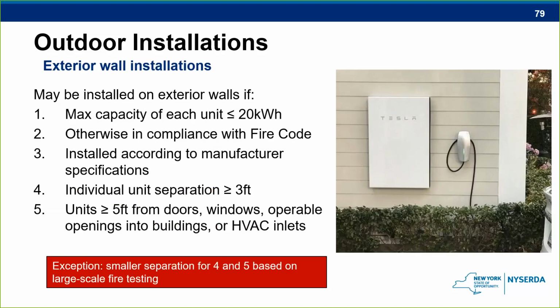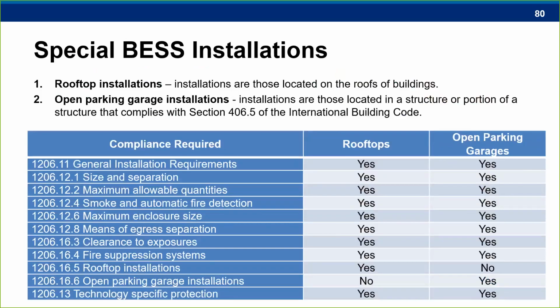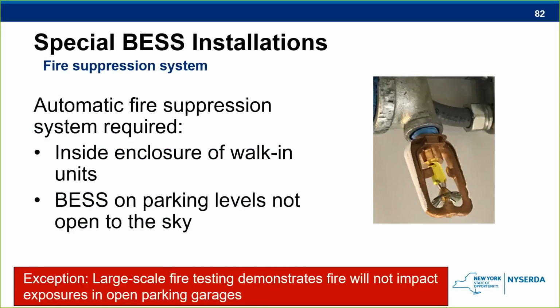Energy storage units can be installed on building walls if they meet the requirements outlined on this slide for the max capacity of each unit at less than or equal to 20 kilowatt hours, the unit separation, and avoiding possible inlets like windows, doors, and of course otherwise meeting code requirements. I alluded to this earlier, but there are also special requirements for projects that are installed on rooftops or open parking garages. They have many of the same requirements we've seen for the other systems, with just a few caveats that I'll go through. These systems are required to have fire suppression inside the units and also on covered parking levels, but automatic fire suppression is not required for energy storage systems on the top level of the parking garage if there's no roof or ceiling, if it's open to the sky above.